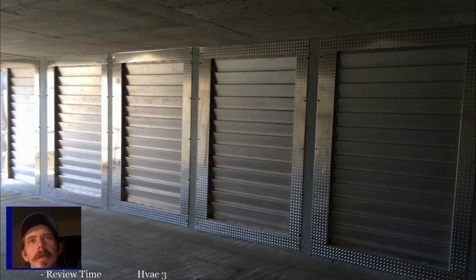For instance, and I can't even remember what they are because this is not how I troubleshoot, but you had an old rule of thumb with reciprocating compressors on what was an acceptable Megger value, what the resistance you could have to ground was on a reciprocating compressor. And when scrolls came out, that value dropped significantly. So again, I can't recall the numbers off the top of my head, and I won't lie to you guys and try and pull them up. But the point is that a scroll compressor can have a smaller resistance value to ground and still be perfectly fine than an older semi-hermetic reciprocating compressor could. So what might test as a fail on a recip will actually be a passing value for a scroll.